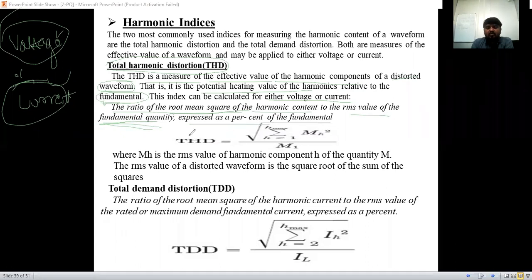So THD, total harmonic distortion, equals the square root of the summation, with limits where H is greater than 1, of MH squared divided by M1, where H is the harmonic order. Here M is the quantity and H is the harmonic component, so MH is the RMS value of harmonic component H of the quantity M, and M1 is the RMS value of the fundamental quantity.